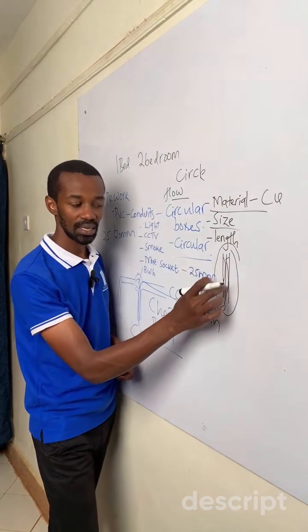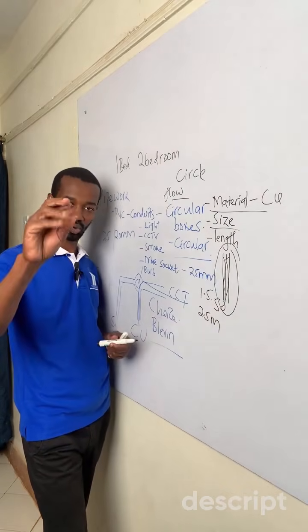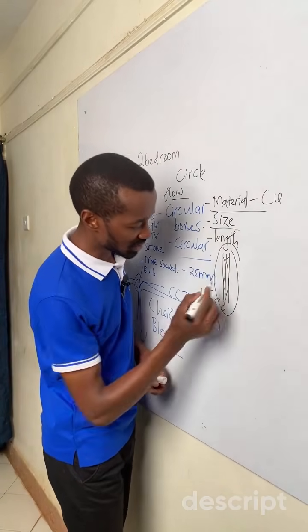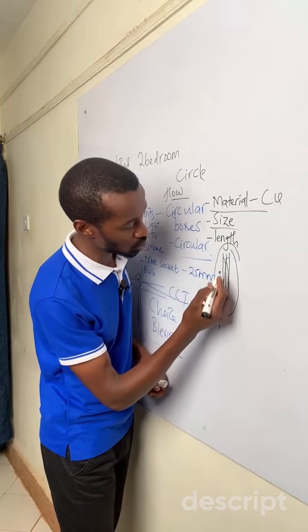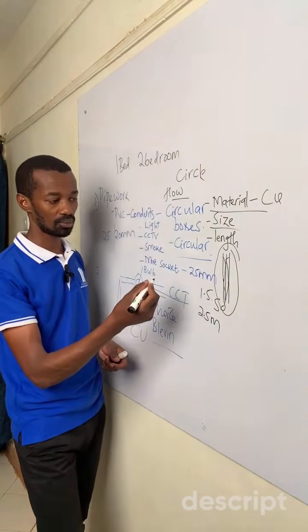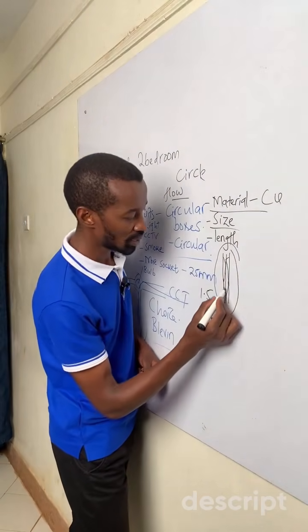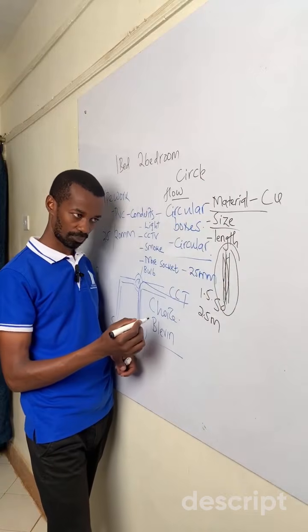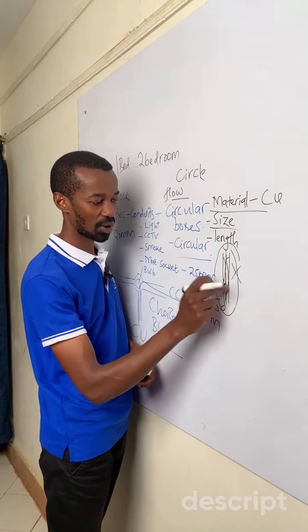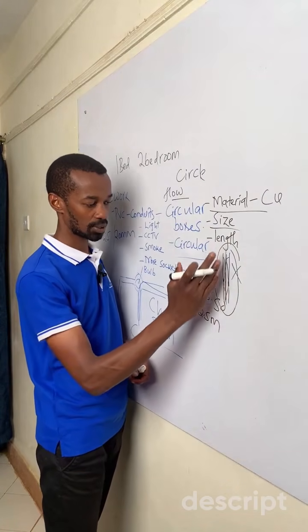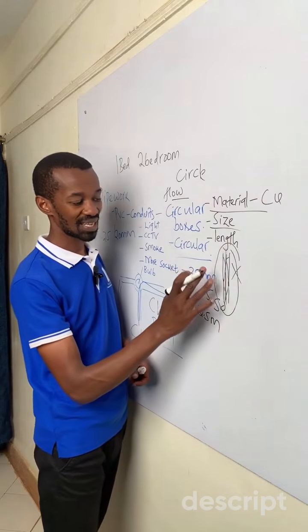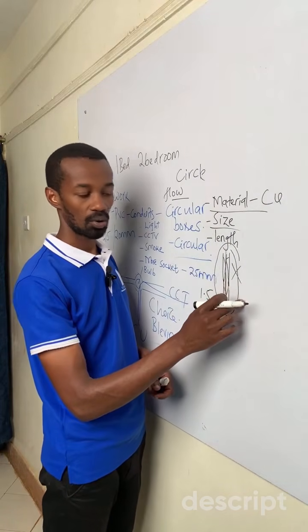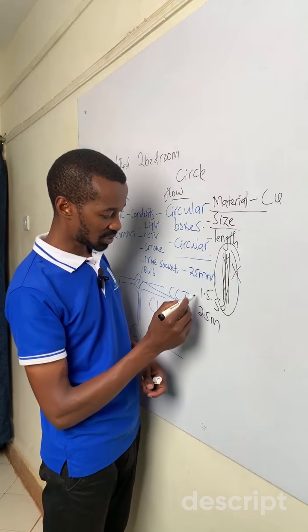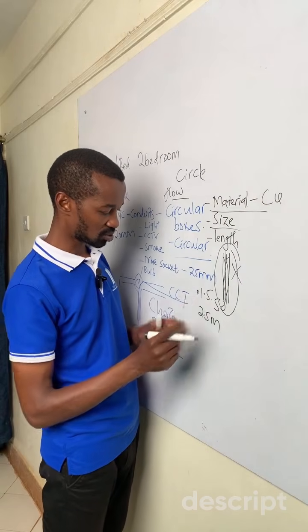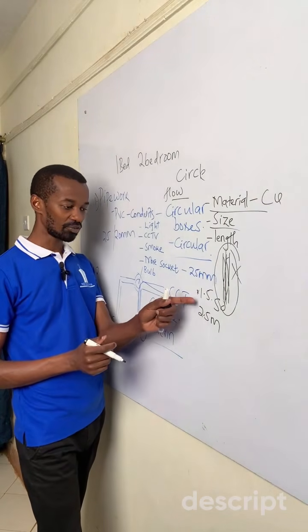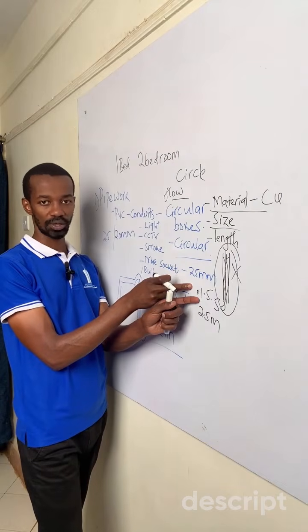They were already burning, melting, and also coming together so that the space was constricted. There's no way you could have pulled the old cables or pulled new installation. So we had to do away with the entire wiring before we could have new wiring. So in the long run, the customer spent a lot. Now, that is the problem of using the wrong size. So the size of the cable matters. If you're going with the lighting, you're supposed to go with 1.5.